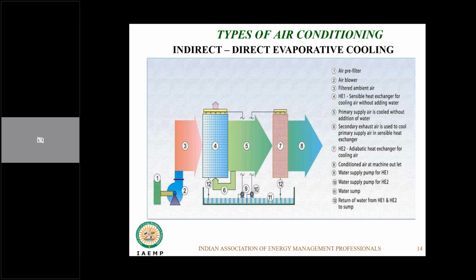But basically, in this heat exchanger there are 2 channels. One for the fresh air coming in, which we want to put in the room, and the other for the exhaust air. This exhaust air is first evaporatively saturated, so it comes to its wet bulb temperature, which for an ambient condition like Delhi would be around 25 in today's scenario. So this 25 and 40, we have 15 degree delta T. This is what sensible heat transfer happens in this heat exchanger here.